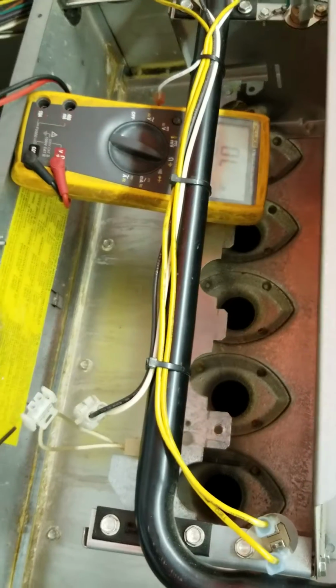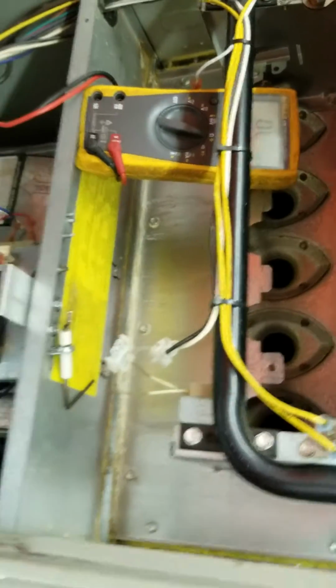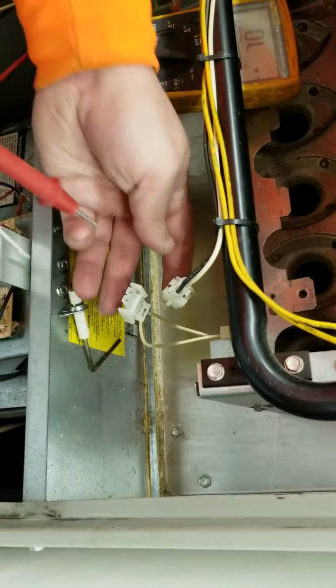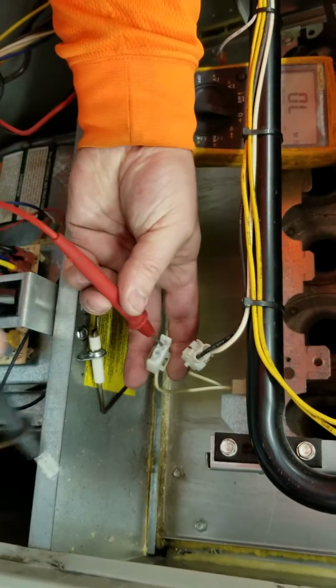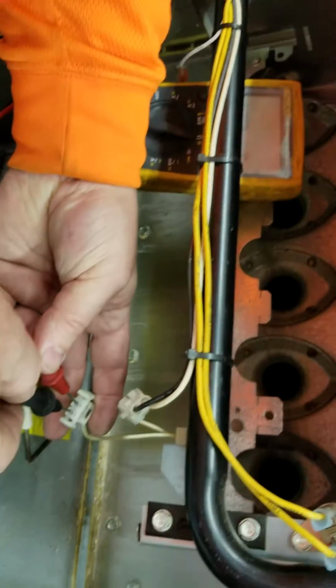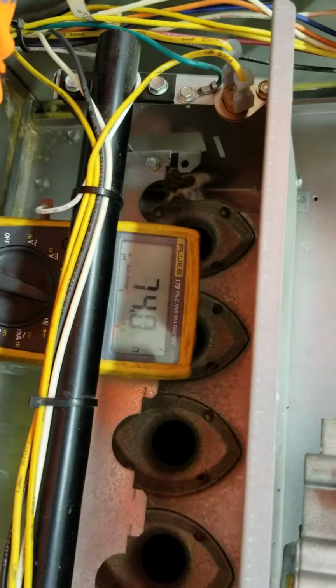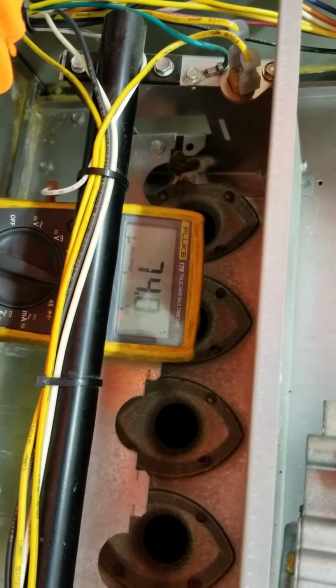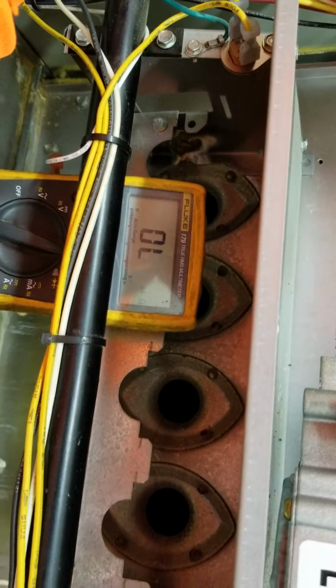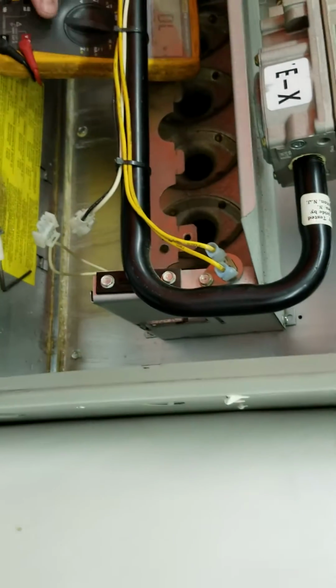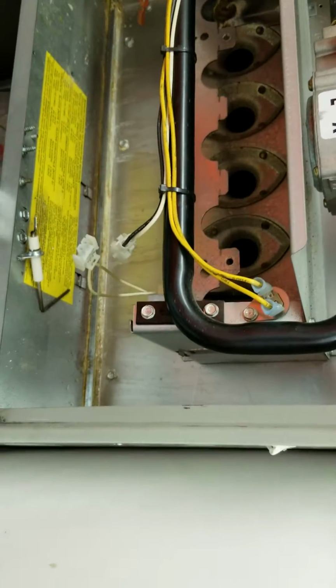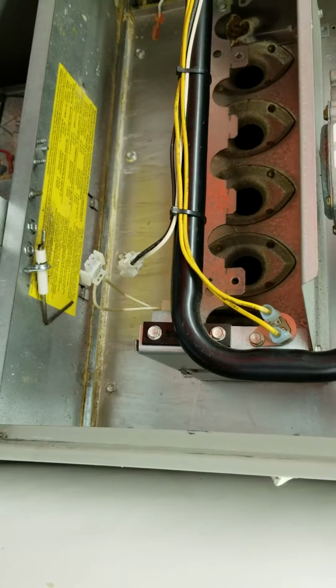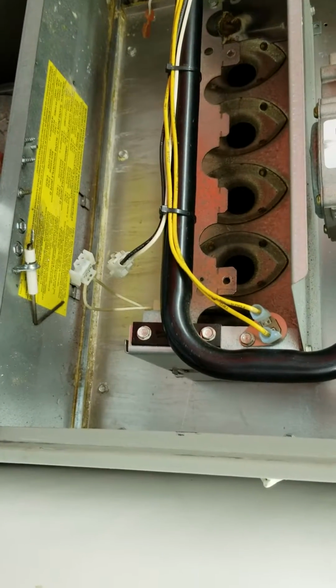We can see it. Go ahead and measure that. One lead in each terminal, because we're measuring the resistance across it. And there's 74 ohms. That's acceptable. When they start approaching 400 ohms, if it gets to 400 ohms, the most chances are it will not work. At 200 ohms, I would question it.